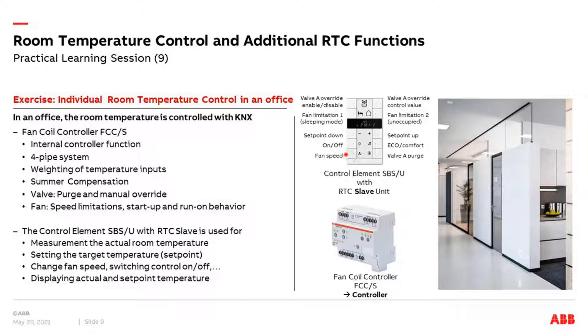We have here a typical office or room, and we want to use heating and cooling in the room with the fan coil controller FCCS — he works as a controller. In the room we have the control element Tenton, which works as a slave. With the rockers we want to do some functions: changing the set point via the rockers, switch on and off, change the operating mode between ECO and comfort, fan speed manual. With one button we want to activate the valve purge, with other buttons the manual override for valve output A — enable or disable and set the value. With further buttons we want to use the fan limitations: fan limitation one in sleeping mode, and fan limitation two when the room is unoccupied.